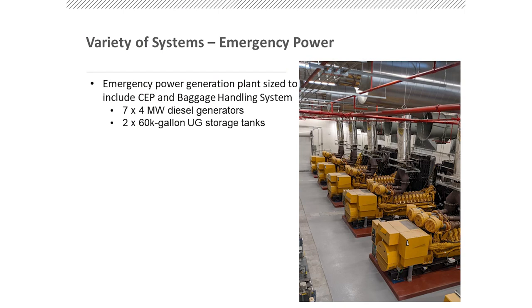The project, as you saw on the map at the north end, includes a very robust emergency power generation system. It consists of 7 4-megawatt diesel generators. The photos may not do them justice, but these are 20-cylinder locomotive diesels, pretty impressive just to stand next to. But the interesting part of this design is that they're sized not just for basic emergency lighting or life safety systems in the south terminal. Basically, most of the south terminal can be carried by this plant, including the baggage handling system, lights, fans, and other systems, which Wade is going to get into talking to you about in a second here.